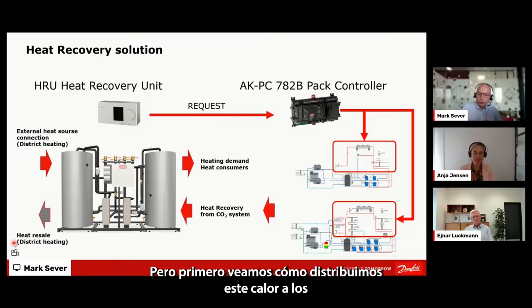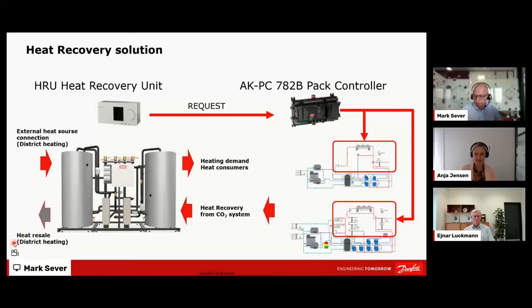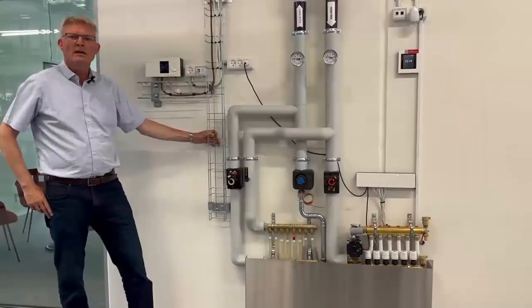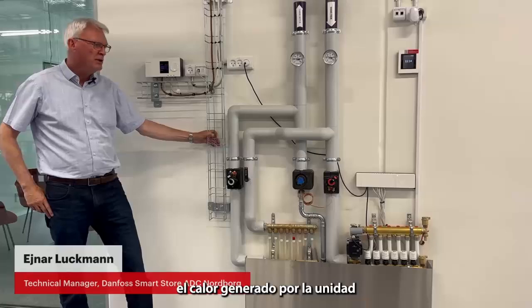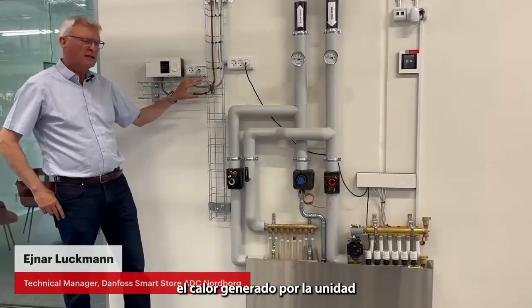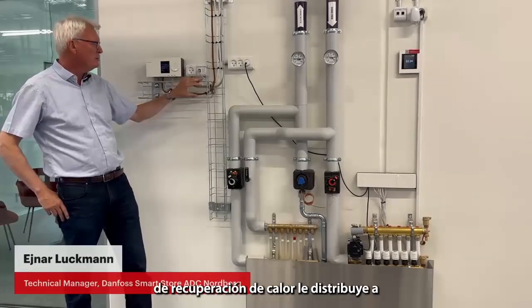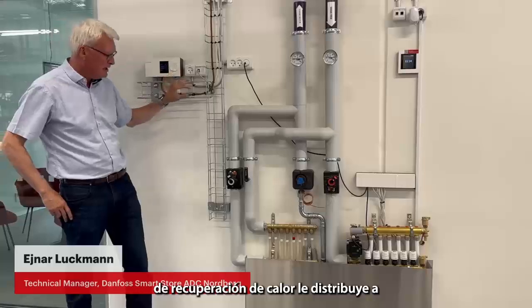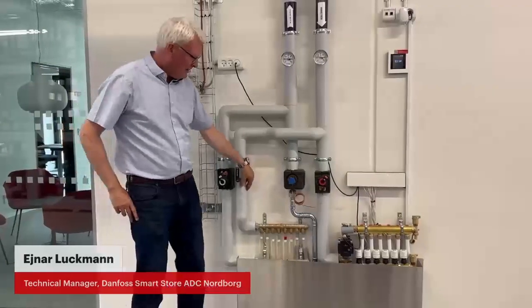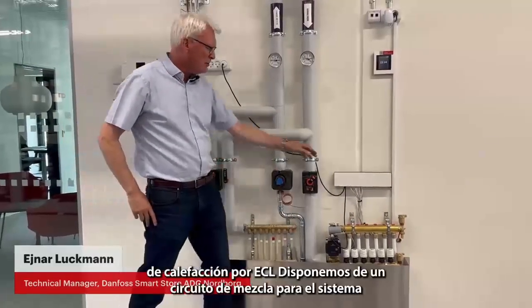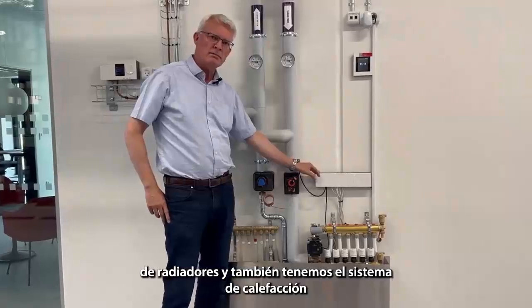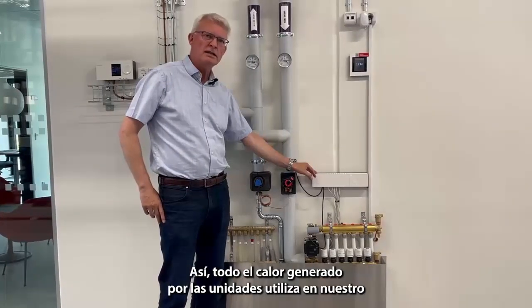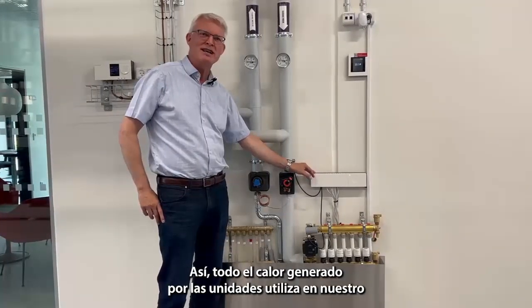But let's see how we are distributing this heat to the consumers first. Heat generated from the heat recovery unit is then distributed to this heating system, where we are controlling the mixing loop and the heating system by ECL. We have a mixing loop for the radiator system, and we also have the Danfoss floor heating system, as can be seen here. So all the heat generated by the packs is used in our own heating system.